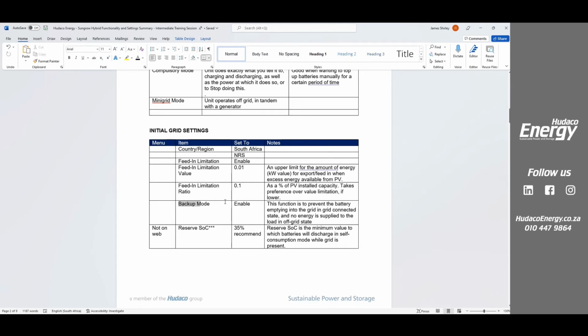What does backup mode do? So I haven't explained that, but let me explain what backup mode does. Backup mode is there to tell the system, do not just dump all your power into the grid. Okay, we have to save some for backup. It's telling the inverter that there's a battery system attached, that there's a backup mode, and do not dump more than the reserve state of charge into our loads. Okay.